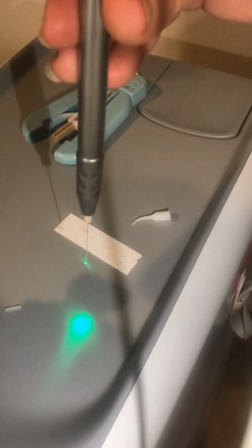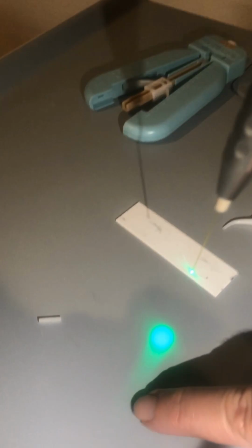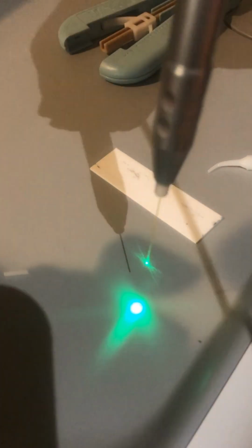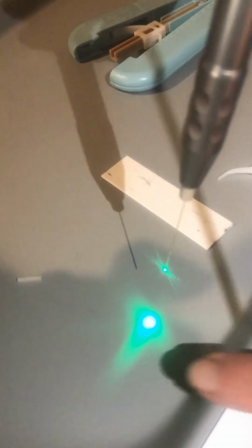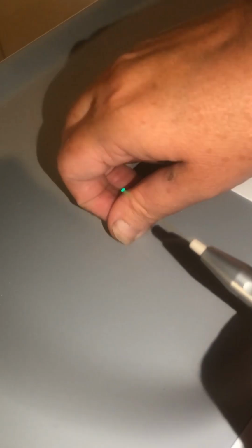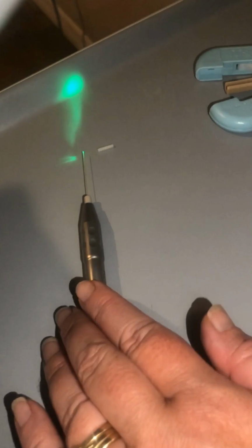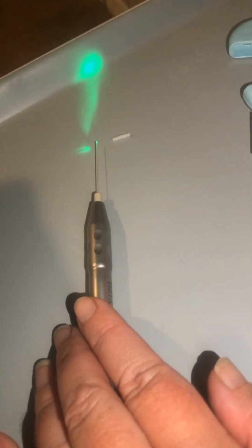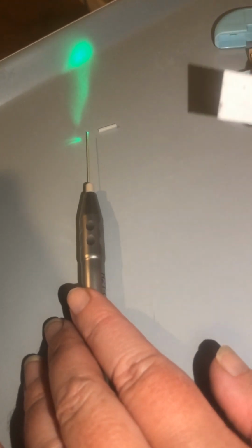And now when you're looking at that, do you see that big comet's tail? This big drag area that's there? That's a loss of energy. We don't wanna see comet tails when we get done cleaving this. We wanna see a nice round green circle with no comet tail when we're doing it. So that means we just need to re-cleave the end of the fiber, which you're gonna do after you've actually used it on a patient. You're gonna cleave off any portion that has actually been exposed to the patient as well.